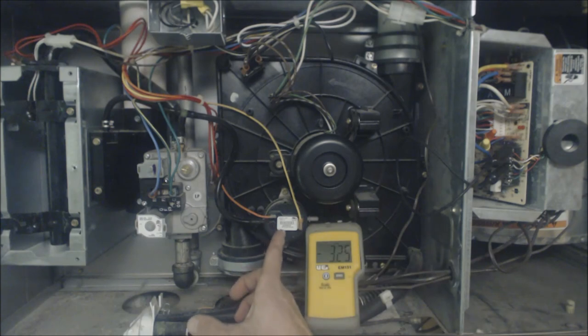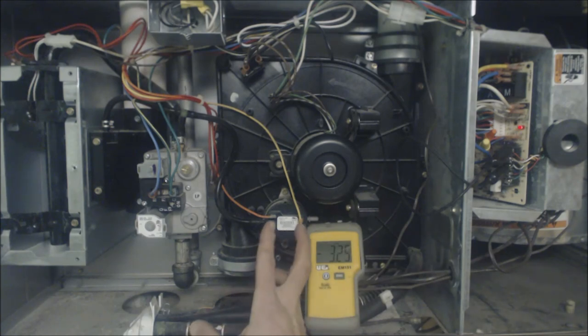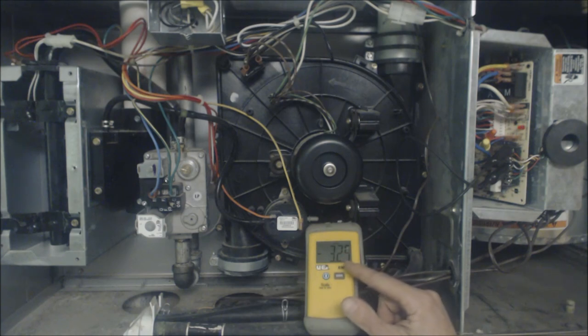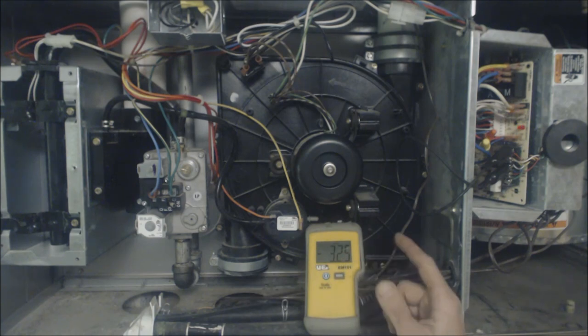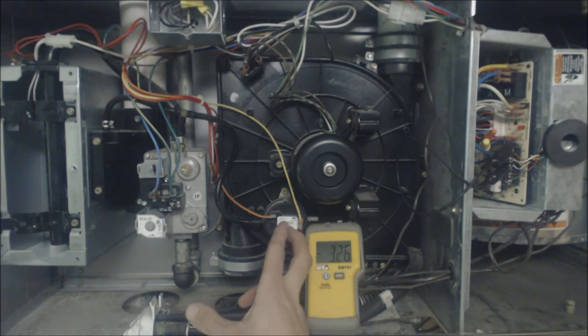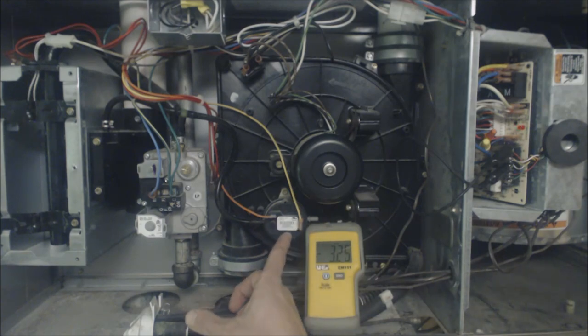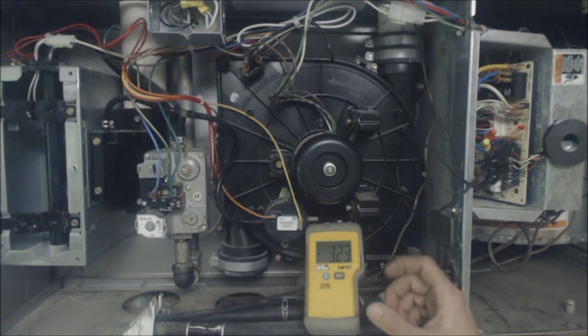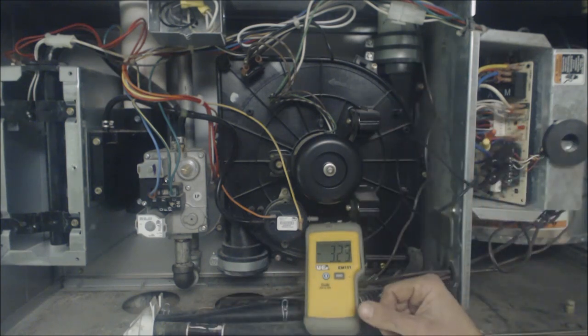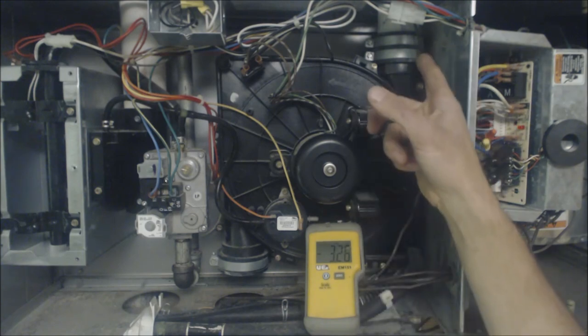Right now if the pressure switch was not closing the electrical contacts with negative 3.24 or 3.26 or whatever it is, if it's not closing these electrical contacts, yes, then the pressure switch is bad, okay. But you want to always be aware, you know, that it could be a couple other things like I said.